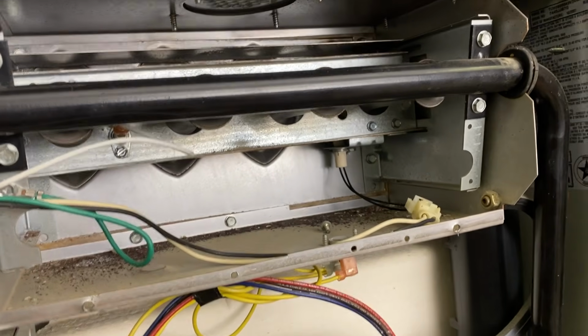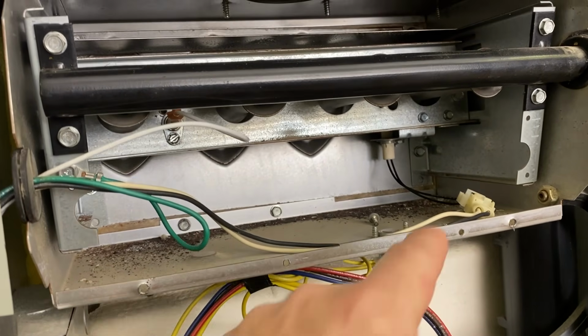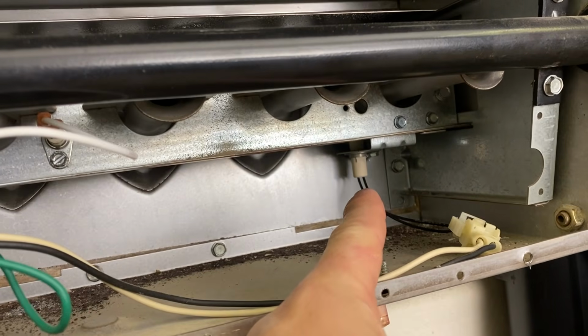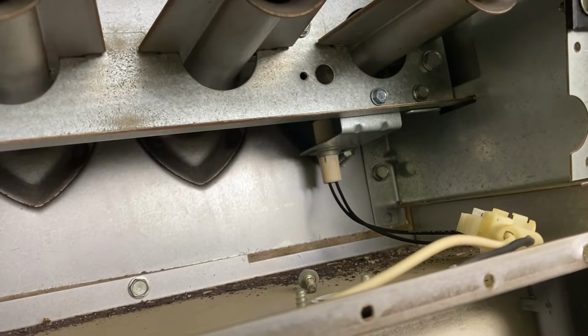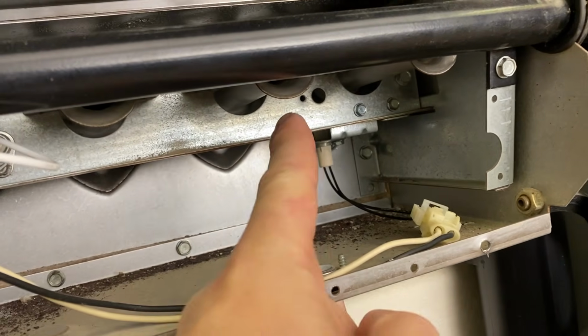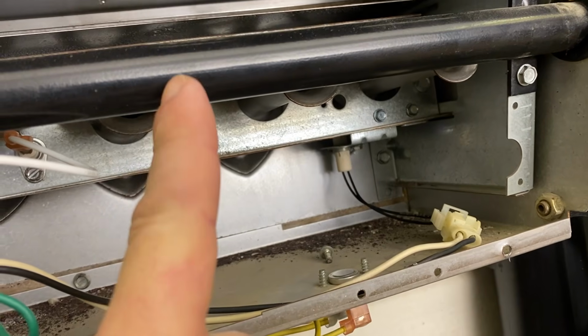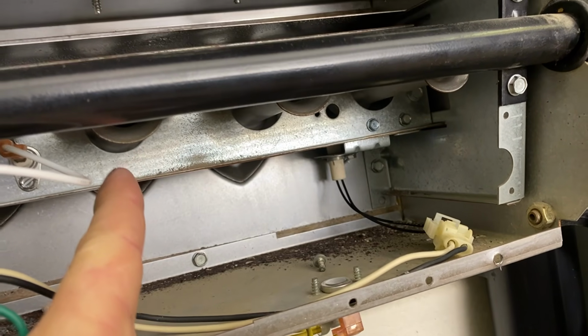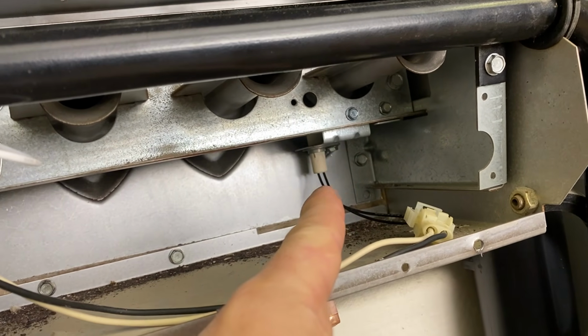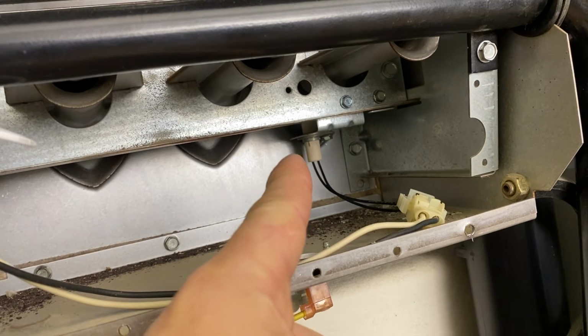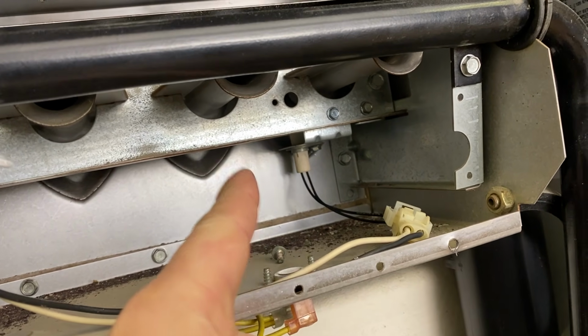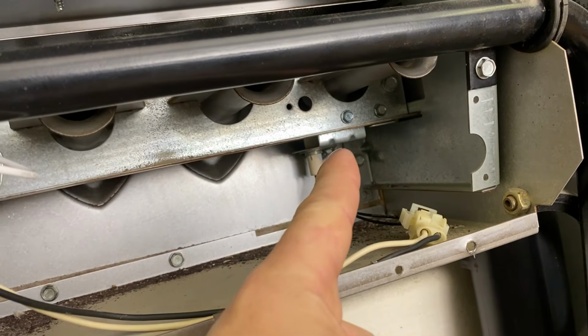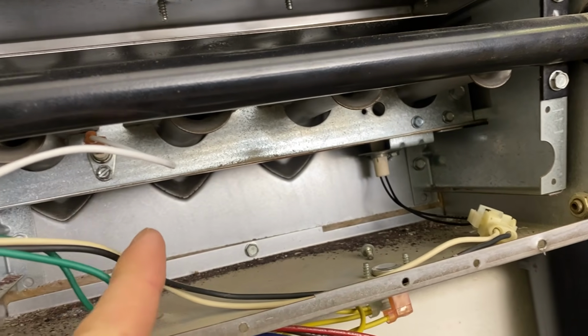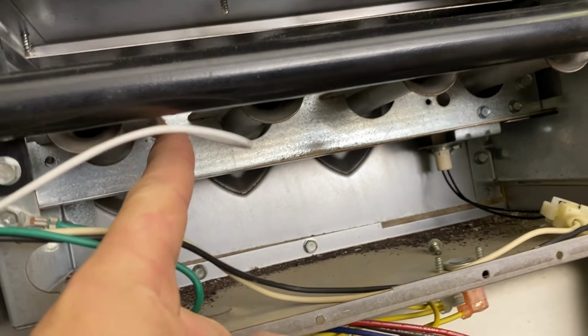Okay, so inside here there are three main components. You have a hot surface igniter back there, sticking up in front of the burners. The burners are these little tubes here. Gas comes in through this tube, shoots through here, and mixes with air, and then the hot surface igniter will light up and glow. That's the next thing you should see, and that will light the burners on fire. There are some spreaders in there and they'll all light. At that point, there is a flame sensor right here.